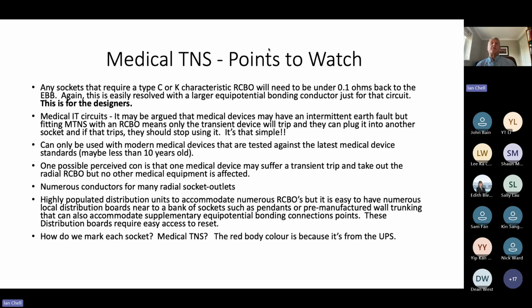One possible perceived con is that one medical device may suffer a transient trip and take the radial RCBO out, but it's important to explain no other medical equipment is affected. The other con is that there are numerous live and neutral conductors for many radial sockets, but this obviously means highly populated distribution units to accommodate numerous RCBOs, but it's quite easy, in my view, to fit sub distribution units nearer to pendant arms and things like that. So I don't know the precise answer to this yet, but I think this is a really easy solution, which electricians can easily solve. And the main point is that you need easy access to reset the RCBOs, okay? So that is a design consideration.